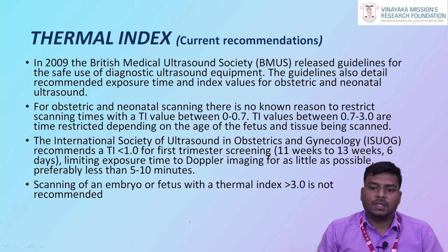Thermal index: current recommendations and future directions. In 2009, the British Medical Ultrasound Society released guidelines on the safe use of diagnostic ultrasound equipment. The guidelines also detailed recommended exposure times and index values for obstetric and neonatal ultrasound. For obstetric and neonatal scanning, there is no known reason to restrict scanning with a TI value below 0.7. TI values between 0.7 and 3.0 are time restricted depending on the age of the fetus and the tissue being scanned.